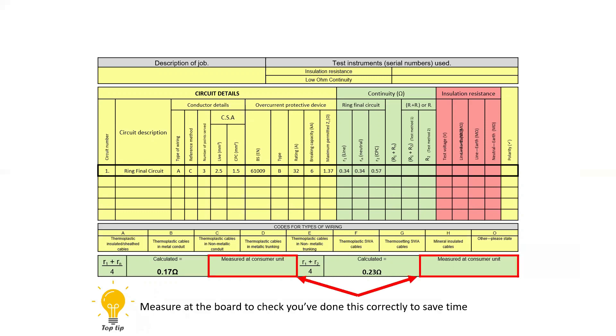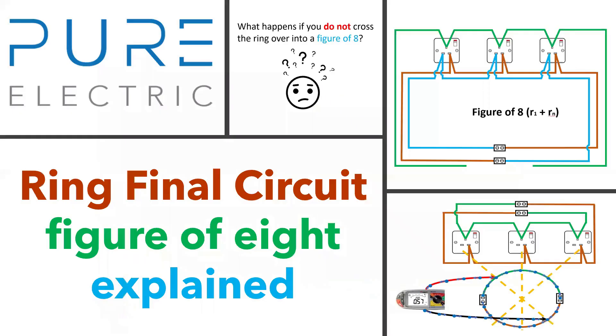One further thing that I suggest which I believe to be best practice is to then measure the R1 Rn and the R1 R2 at the board first while you are there and have it connected in the figure of eight before you start working your way around the socket and finding out that you haven't connected or calculated the ring correctly. In my next video I'll show you why it's so important to connect the ring into the fabled figure of eight and how you are fault finding by doing so.